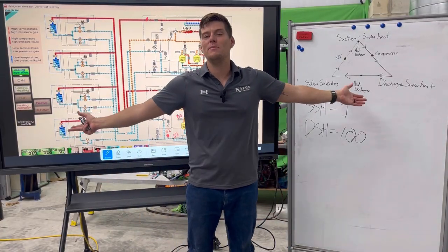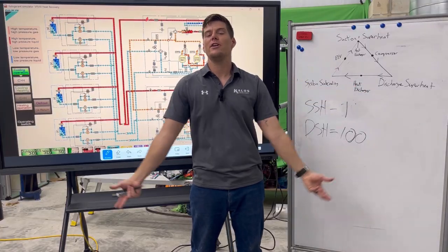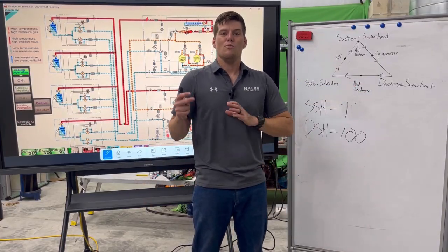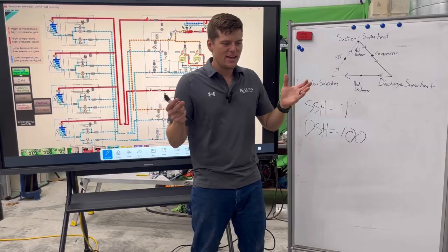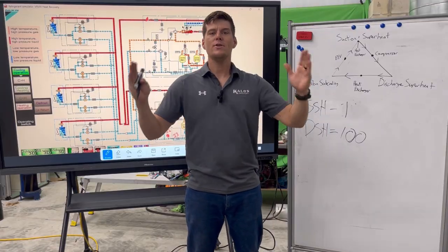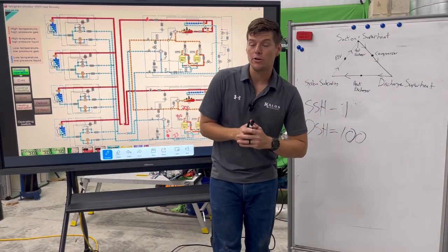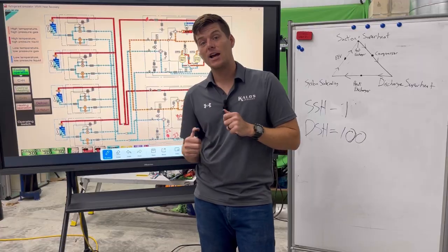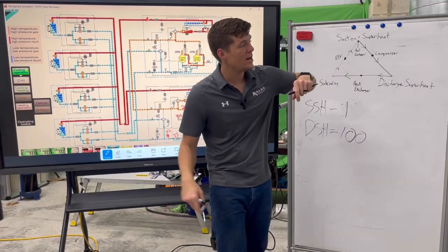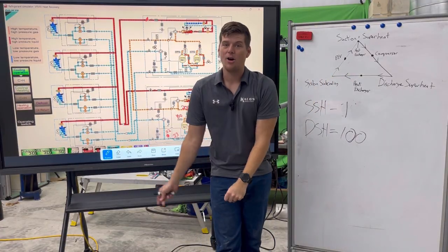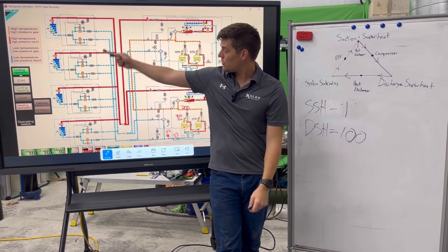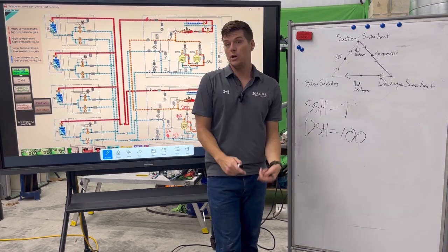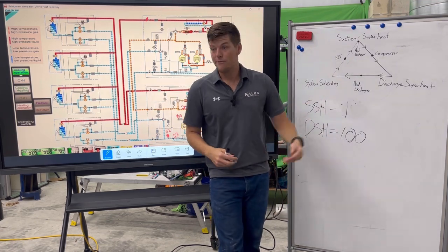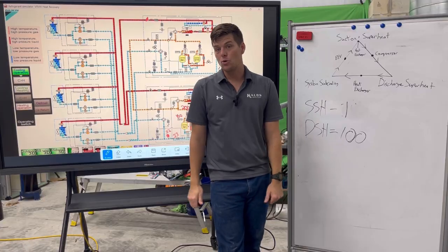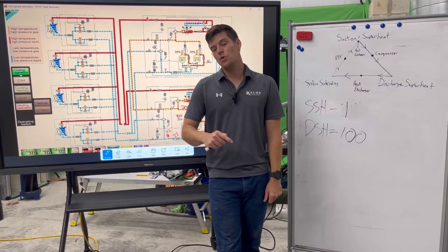Now, every compressor is going to be different. Everybody likes a different number, and I get it, right? Why do we have a range? Why is there from here to here, right? The reason there's a range is because this is what we call an inverter compressor. Inverter compressors are designed to what? Modulate speeds. They're designed to go up and they're designed to go down. And based upon how many of these indoor units are actually calling for liquid refrigerant, or maybe liquid refrigerant and also hot gas, if they're heating and cooling at the same time, that number is going to change.